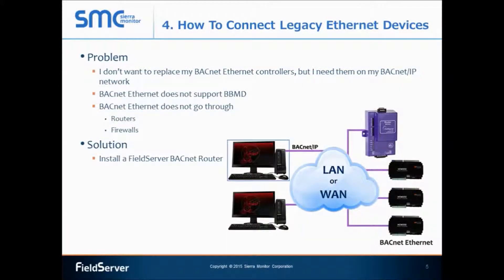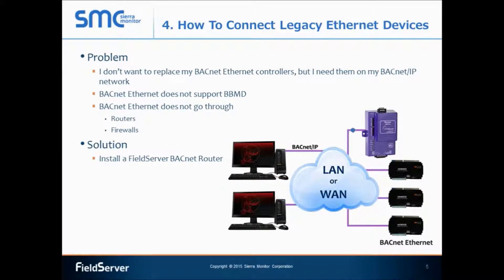Use case number four: how to connect legacy Ethernet devices. Even though most devices or controllers that ship today support BACnet MSTP and/or BACnet IP, many buildings have older devices and controllers based on BACnet Ethernet that are still functioning and providing value. As a facilities manager, I have legacy BACnet Ethernet controllers that I want to connect to my BACnet IP network, but I don't want to and cannot replace them due to costs. BACnet Ethernet does not support BBMD, or BACnet Broadcast Management Device — a key building block of a modern multi-site management framework. The FieldServer BACnet router can connect legacy BACnet Ethernet devices to the modern BACnet IP backbone, supporting BBMD and acting as a proxy for the legacy devices. Once configured, I will have full transparency of my BACnet Ethernet devices on my BACnet IP network.